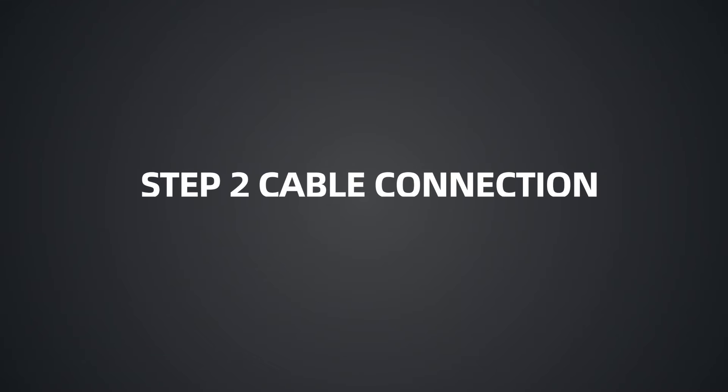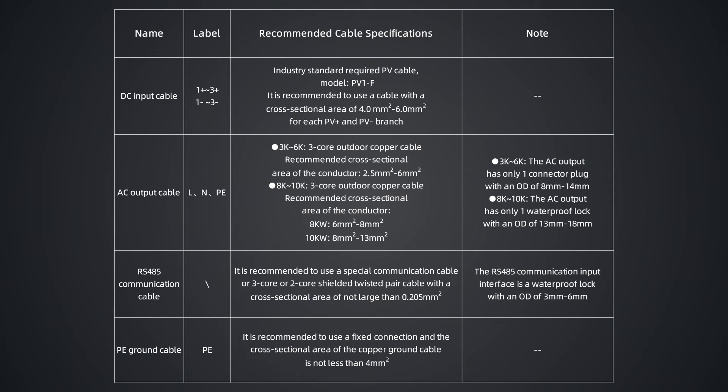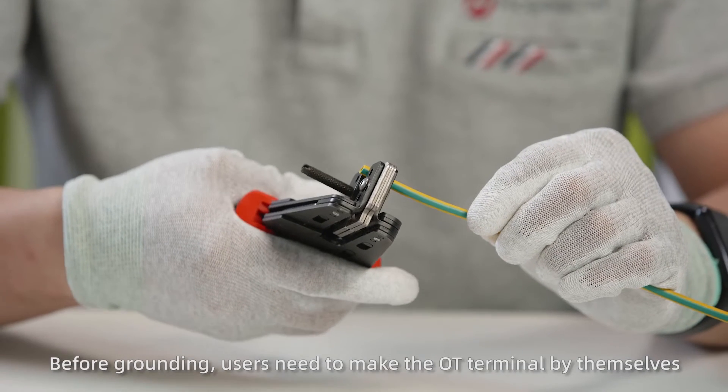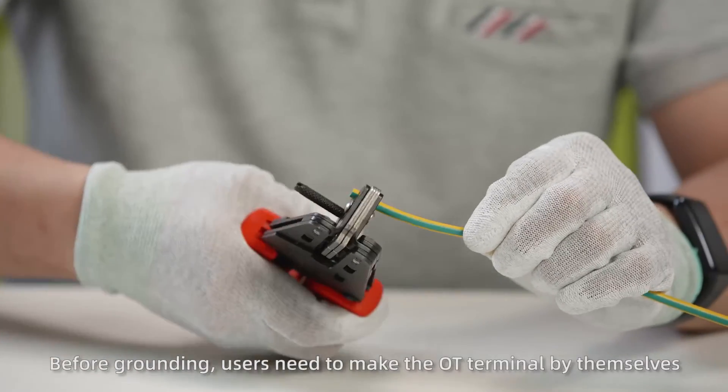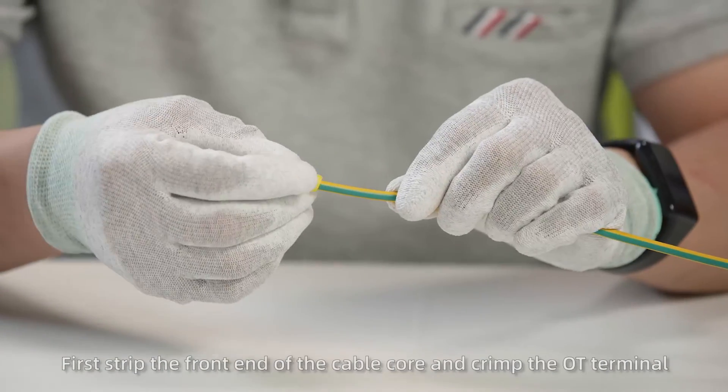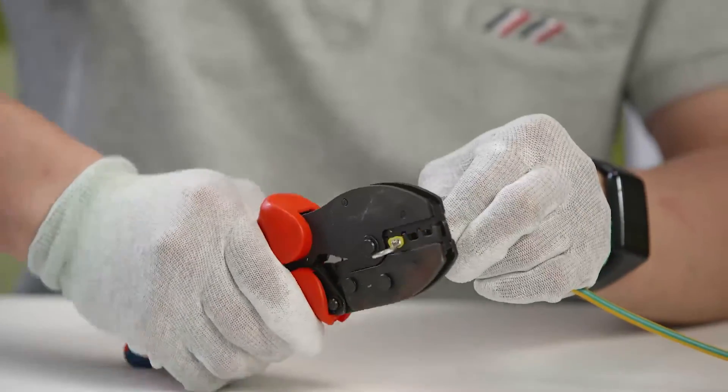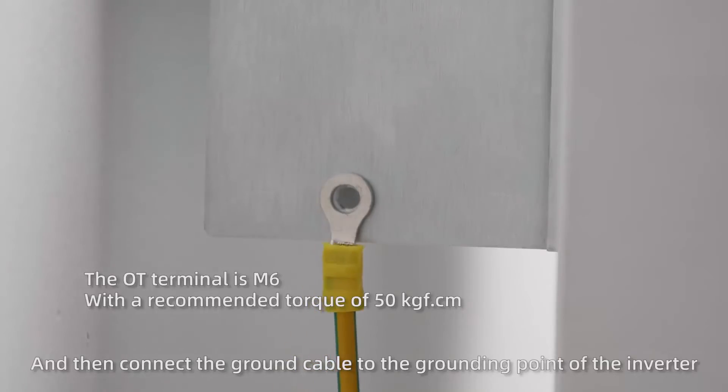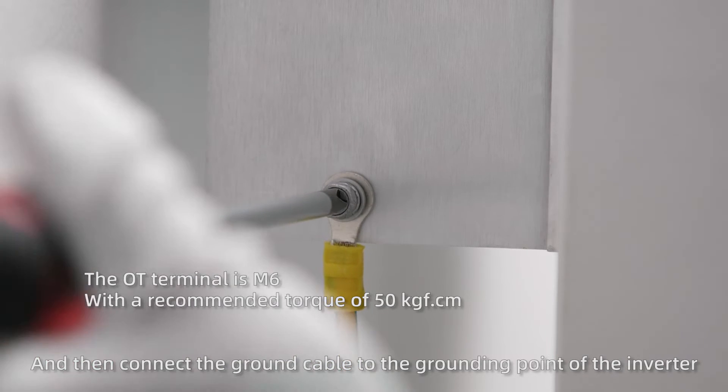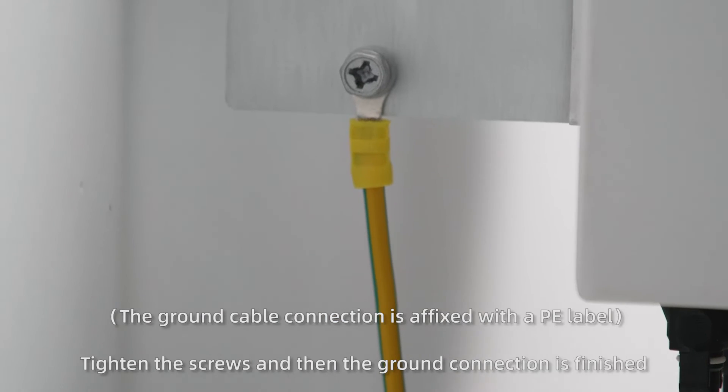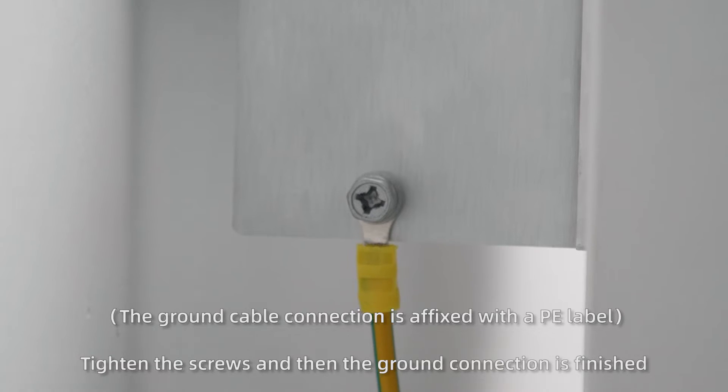Step 2 Cable Connection. First, connect the ground cable. Before grounding, users need to make the OT terminal by themselves. Strip the front end of the cable core and crimp the OT terminal. Then connect the ground cable to the grounding point of the inverter. Tighten the screws and the ground connection is finished.